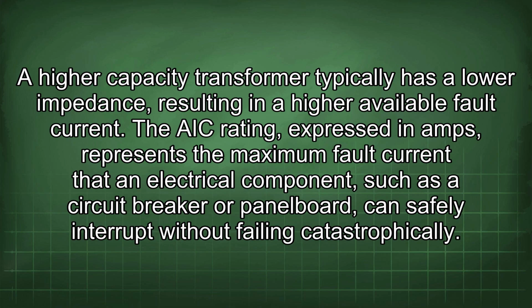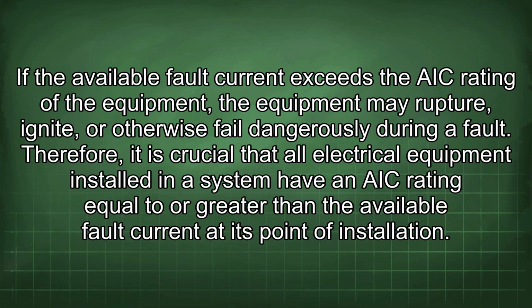The AIC rating, expressed in amps, represents the maximum fault current that an electrical component, such as a circuit breaker or panel board, can safely interrupt without failing catastrophically. If the available fault current exceeds the AIC rating, the equipment may rupture, ignite, or otherwise fail dangerously during a fault. Therefore, it is crucial that all electrical equipment installed in a system have an AIC rating equal to or greater than the available fault current at its point of installation.